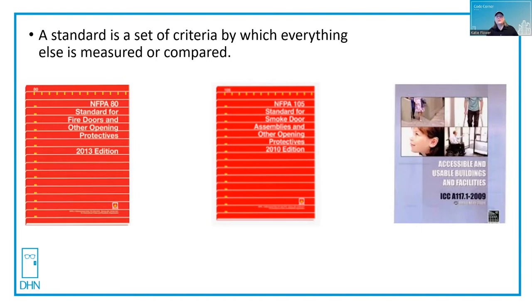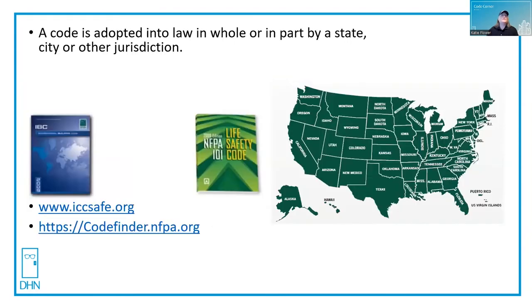The code is going to tell me where I need a fire door and what that rating needs to be, and if there are any exceptions to the standard. Other standards that we use in this industry include NFPA 105 for smoke and draft control and ANSI A117.1 for making buildings accessible to meet the requirements of the Americans with Disabilities Act — just a few that are referenced by our codes.